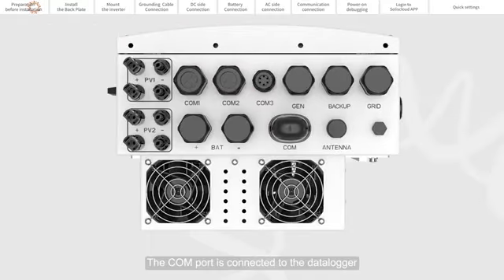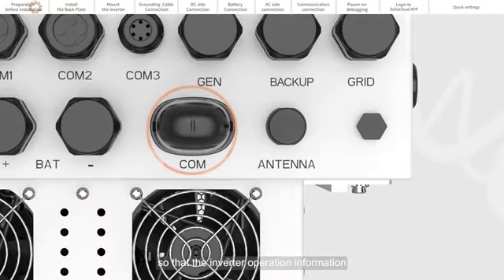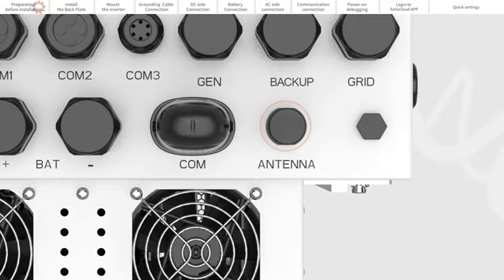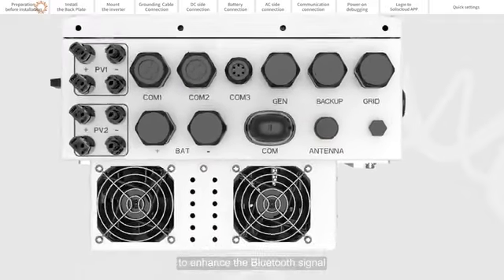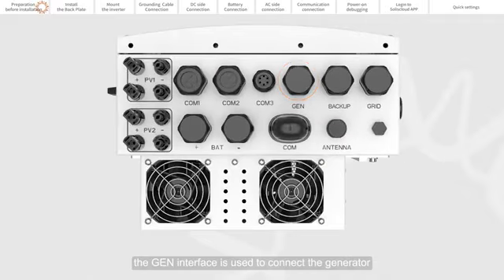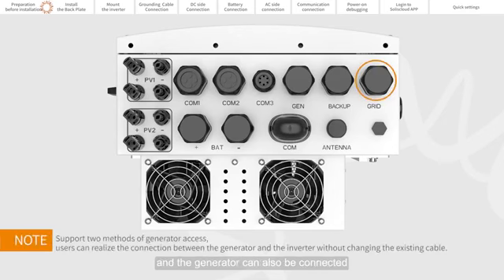The COM port is used to connect the data logger, so that the inverter operational information can be uploaded to the SolisCloud platform. The antenna port connects the antenna to enhance the Bluetooth signal. The GEN interface is used to connect to the generator. The BACKUP port is used to connect to the backup load. The GRID port is used to connect to the grid, and the generator can also be connected to the grid port through the automatic transfer switch.